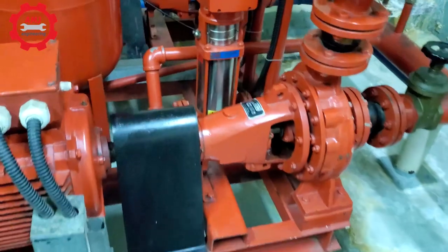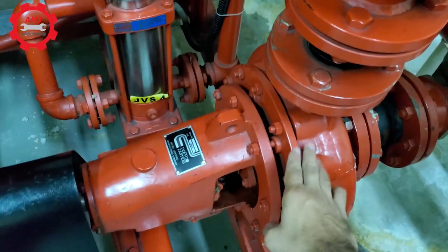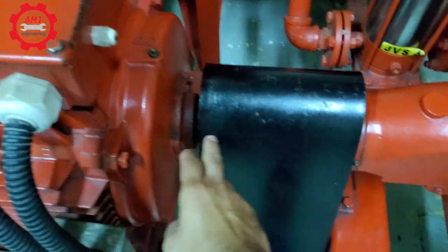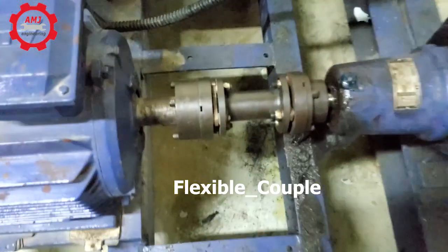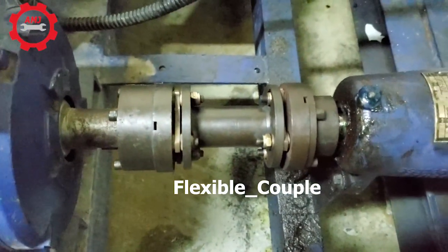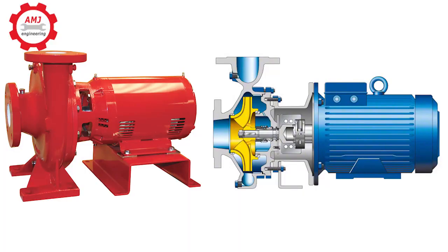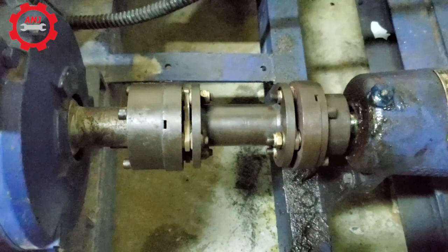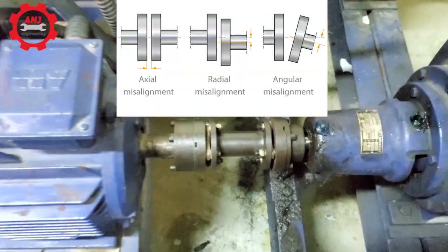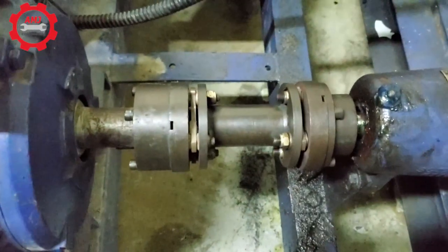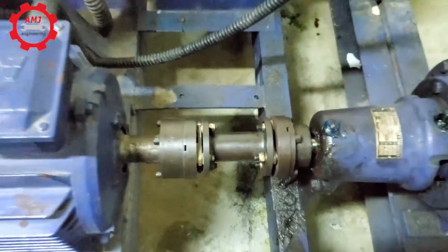A flexible coupled end suction pump, as in our case here, has the impeller and the motor shaft separated by a flexible coupling. A close-coupled pump has the impeller directly mounted to the motor shaft without any coupling in between. The benefit of using a close-coupled pump is that the alignment of the motor shaft to the impeller is fixed. However, a flexible-coupled pump can become misaligned during maintenance. This can create issues if not properly reassembled by trained personnel.